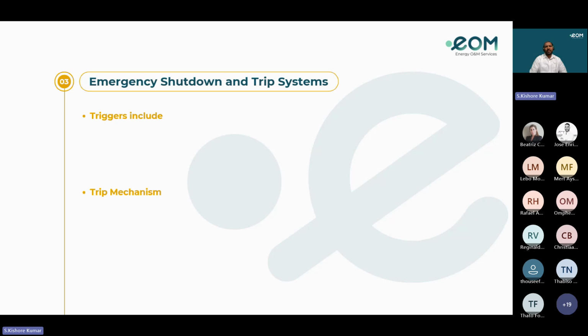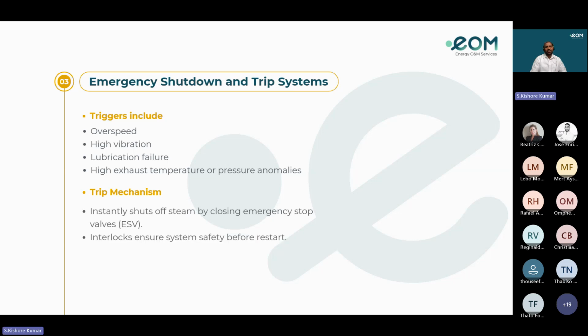Coming to the emergency shutdown and trip systems. The purpose is to protect the turbine and plant in case of unsafe conditions. Triggers include overspeed, high vibration, lubrication failure, high exhaust temperature, or pressure anomalies. The trip mechanisms instantly shut off the steam by closing emergency stop valves, and interlocks ensure safety before restart. Also, never bypass the trip systems, because it will lead to catastrophic accidents. Whenever an outage is completed, make sure all the trip systems are active, and check that they respond well and trip properly based on the trip conditions.